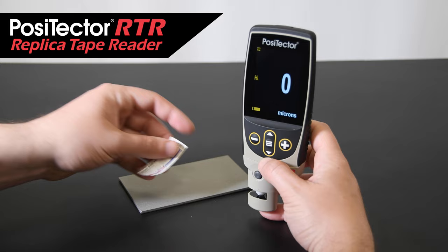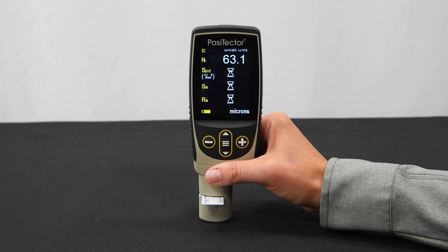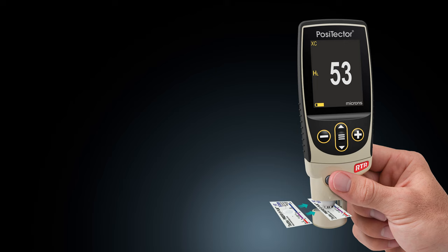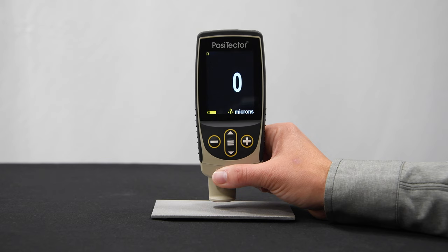DeFelsko's other solution for measuring surface profile, the PosiTector RTR replica tape reader, uses industry standard Testex tape to measure profile height. Models are also available that can create 3D images from the replica tape to measure peak count and other surface profile parameters. Learn more about the PosiTector RTR in the How to Use Replica Tape to Measure Surface Profile video at the link in the description below.